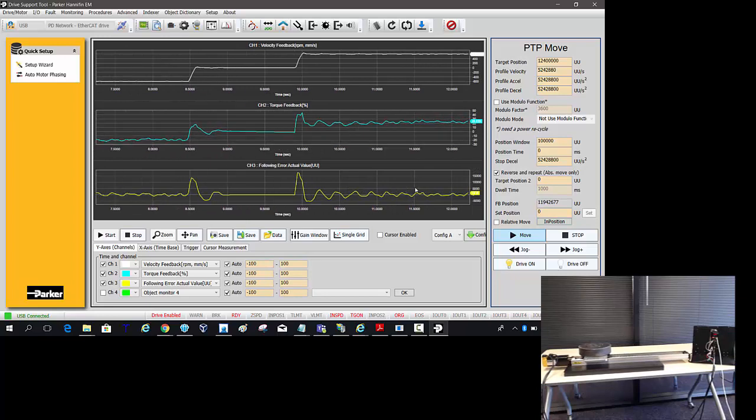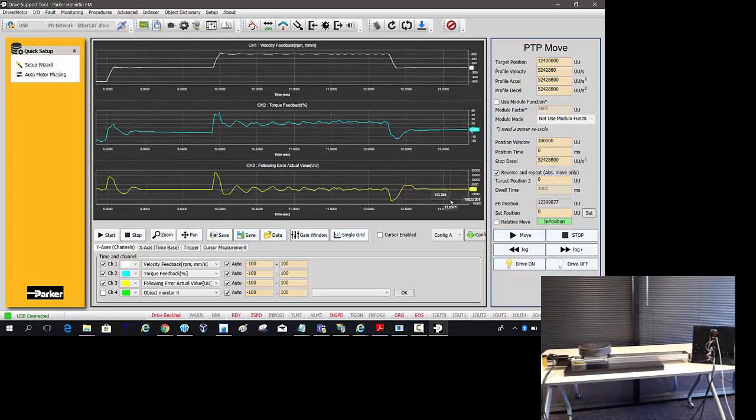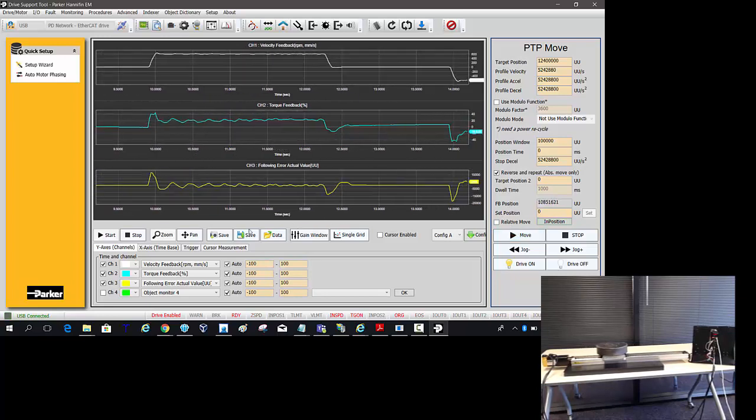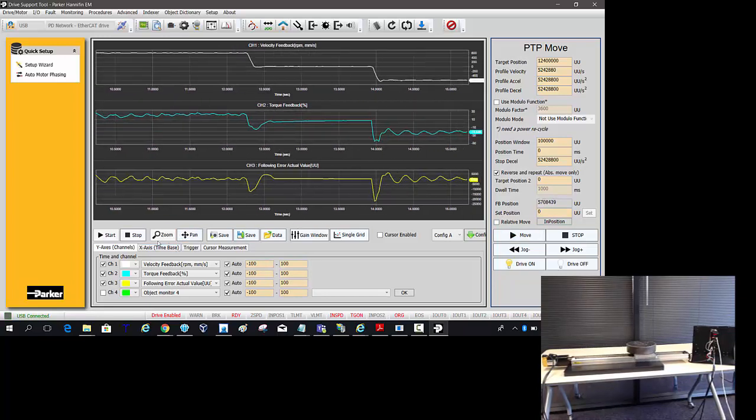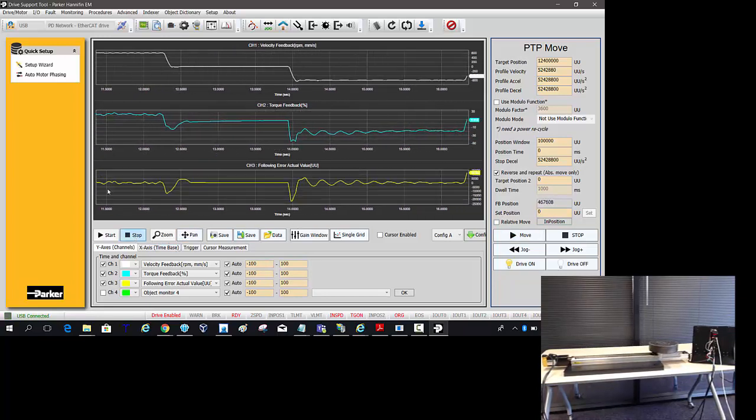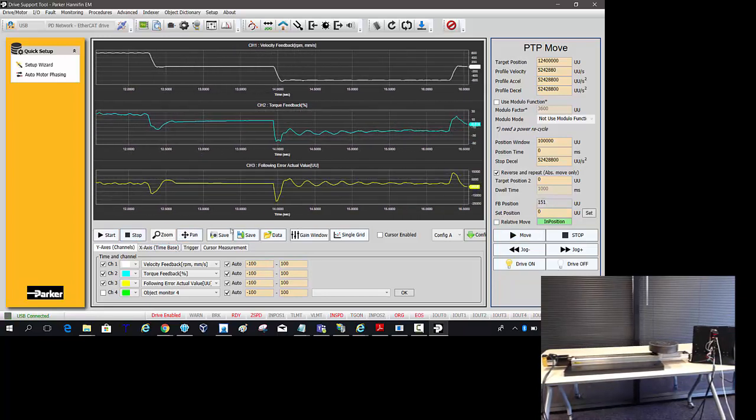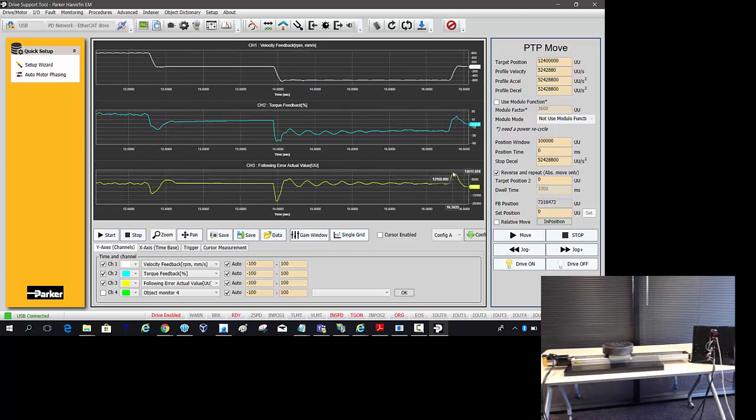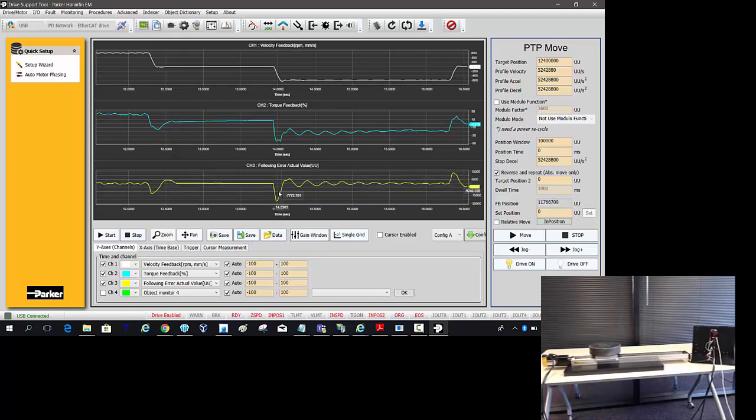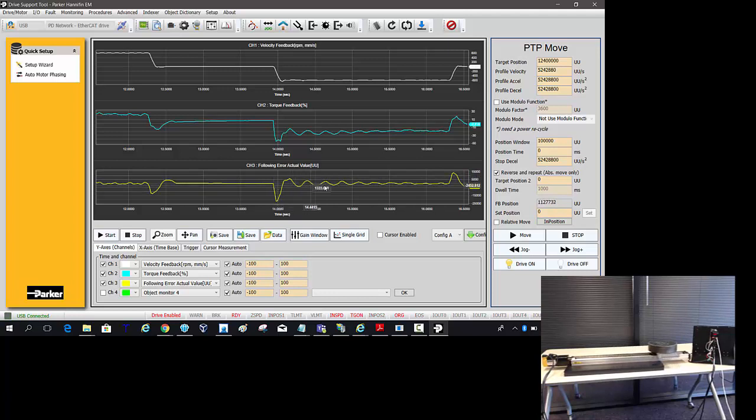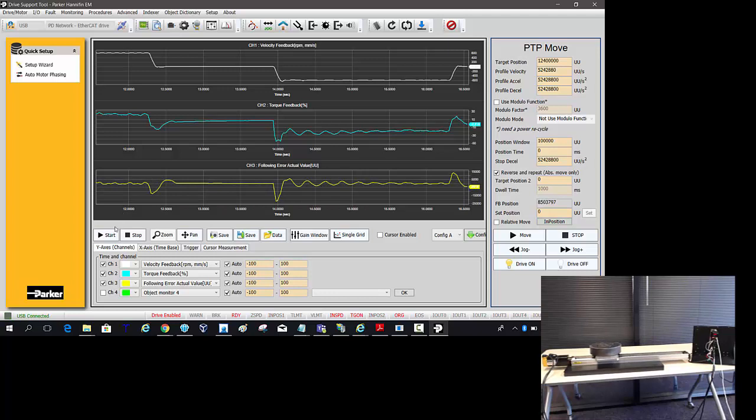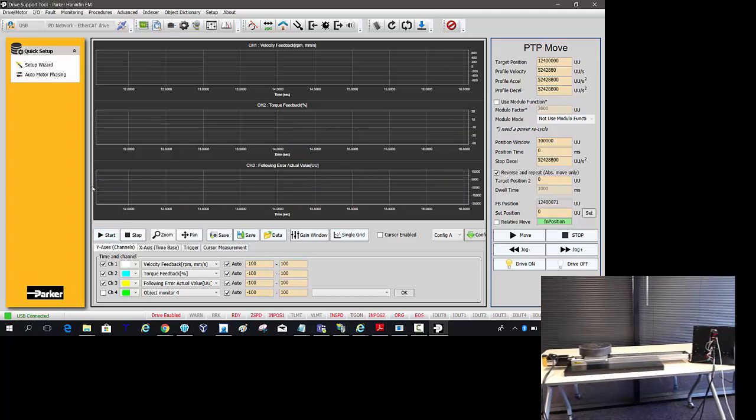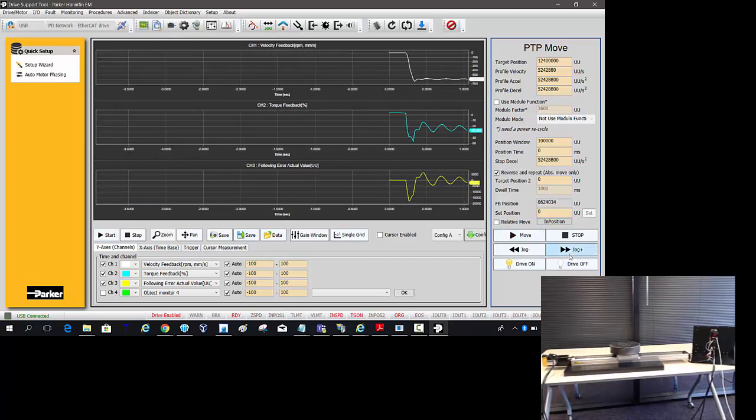So now you can see while we're dynamically moving it's around 15,000 counts when we start to accelerate. And that's normal. But then we settle into position that you see a little bit of ripple here. So how can we better improve that?